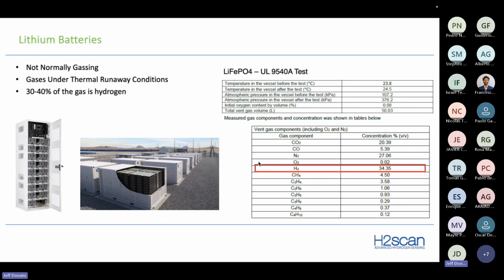So, all kinds of mitigation strategies are already built into these containers. Obviously, they're monitoring heat, monitoring smoke, monitoring for fire, also monitoring gas and activating deflagration vents and all kinds of safety systems that go on with lithium batteries. But obviously, we typically find that hydrogen sensing is put in at the manufacturer level for energy storage. But we're finding in the data centers and UPS, a lot of times the hydrogen systems aren't installed at all. So that's something that we're hoping to take a correction on in the industry to say more safety is better, the more secondary detection systems you have in place for lithium batteries is better. Obviously, when dealing with UPS systems, we also deal more with personal safety than we do with just asset protection.